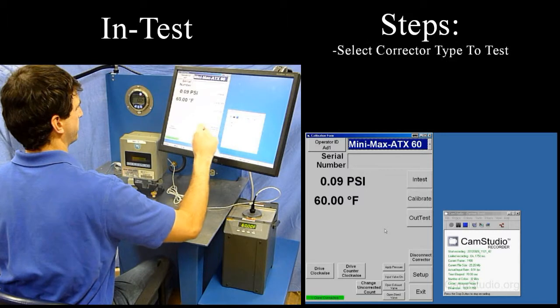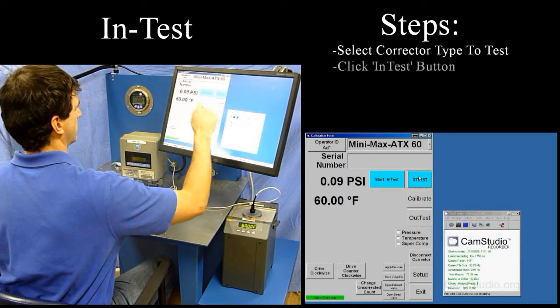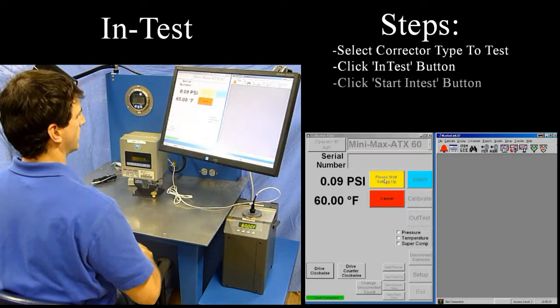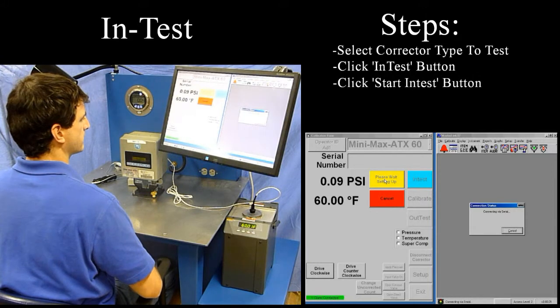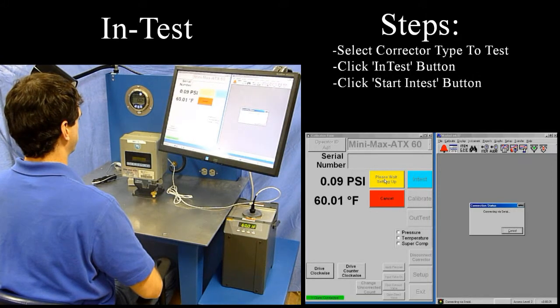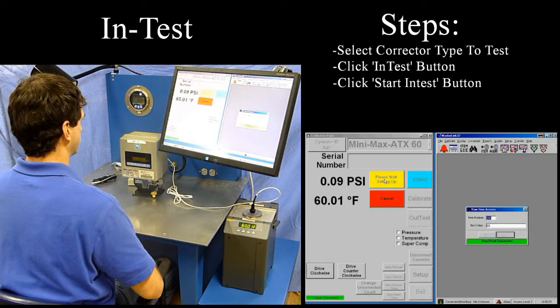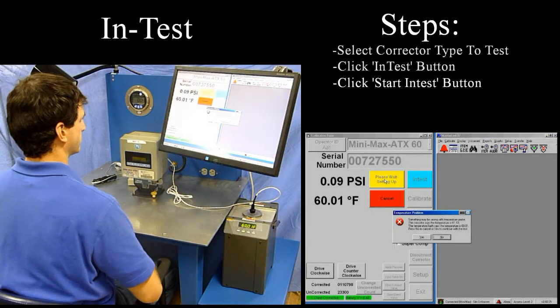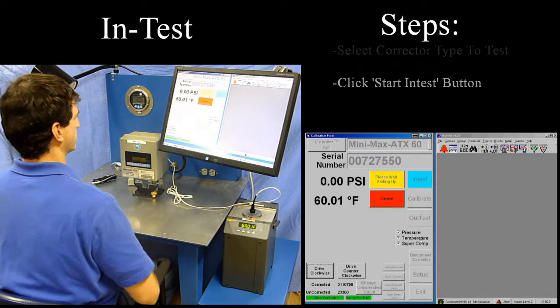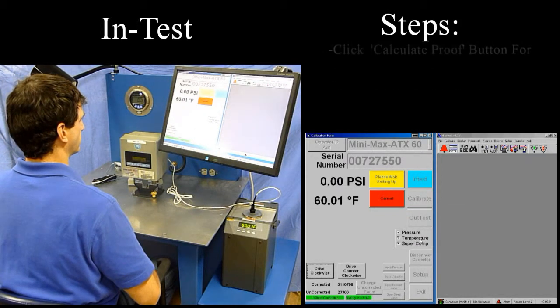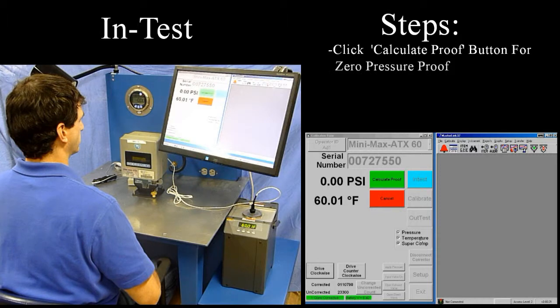The operator selects the appropriate corrector model within the Measurement System software user interface and presses the In-Test button on the touchscreen monitor. Once the Start In-Test button has been pressed, the software connects to the corrector to retrieve information including corrector serial number, corrected and uncorrected counts, battery voltage, and the corrector's capabilities, whether it corrects for pressure, temperature, and/or super compressibility.